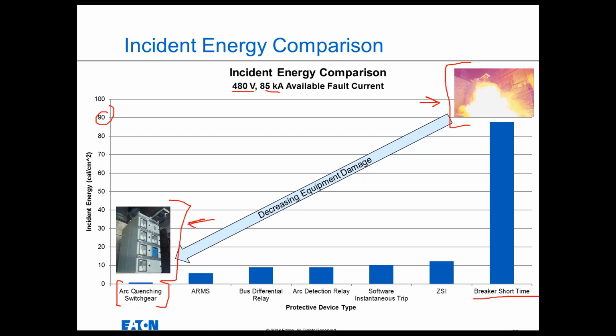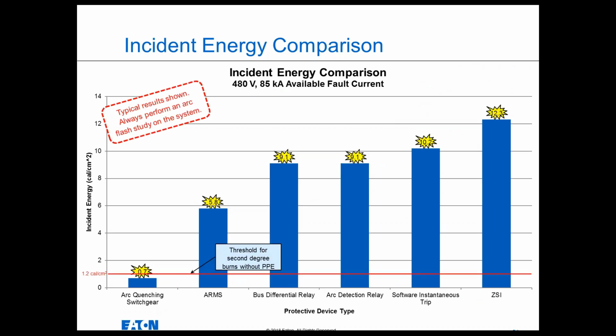I could show you a video of that testing, but it's kind of boring because nothing happens. This is the fun stuff to watch up here, as long as it's under test and not accidentally occurring. So I'm going to get rid of that breaker short time column just to get a little bit more granularity. So again, at 480 volts and 85 kA, zone selective interlocking comes in at about 12.3 calories per centimeter squared. Software instantaneous trip at about 10.2.